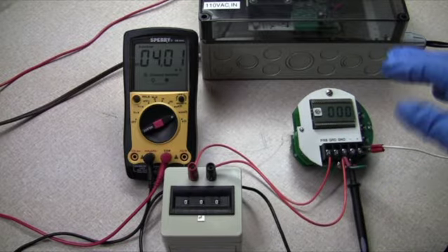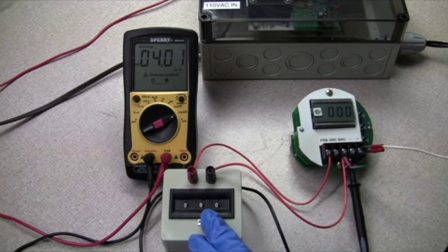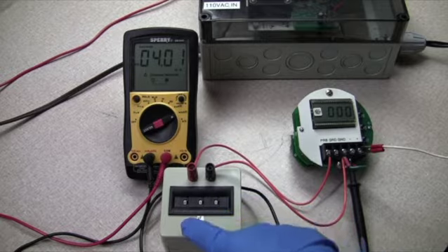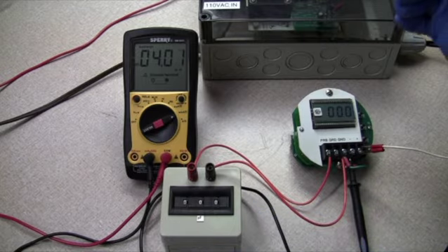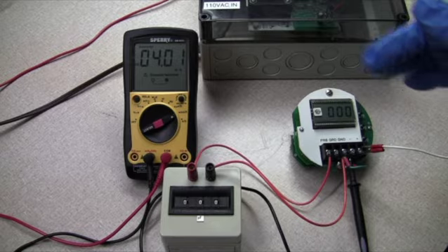In the field, you're going to be doing this on liquid. Right here we're using the capacitance substitution box. I had already pre-calibrated this for low being 0 picofarads and 100% being 200 picofarads. So right now your liquid would be at the bottom of the probe or not even touching the probe.